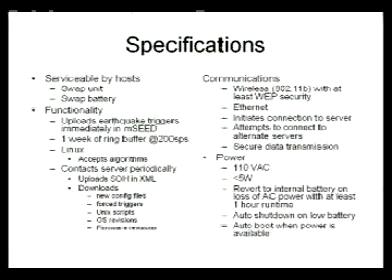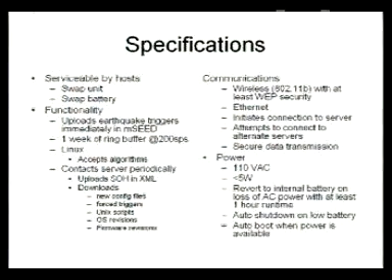It has to have a week of data on the instrument in a memory buffer at 200 samples per second. The idea here is if an earthquake occurs and we lose connectivity on the instrument, we want to be able to go back into that buffer and get data. It's Linux, actually a micro version of Linux for low power, but we wanted to be able to install algorithms like an early warning algorithm if we feel comfortable that this is an area in which we want to go. Every hour, and you can configure it, it'll send home a state of health message in XML. And that tells us its battery and, I'll show you an example in a moment.